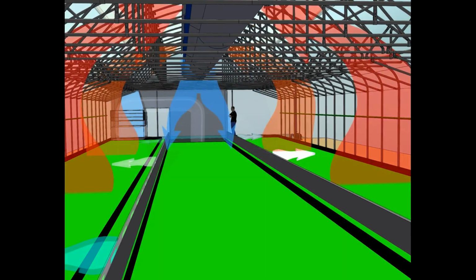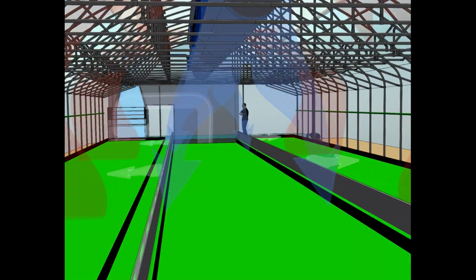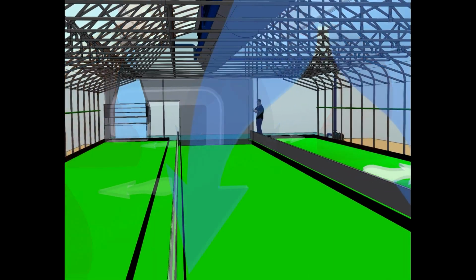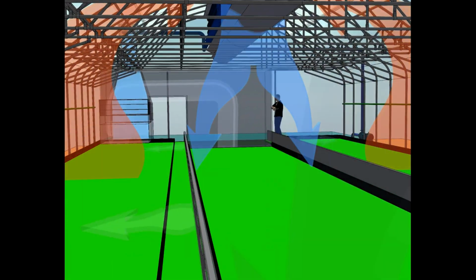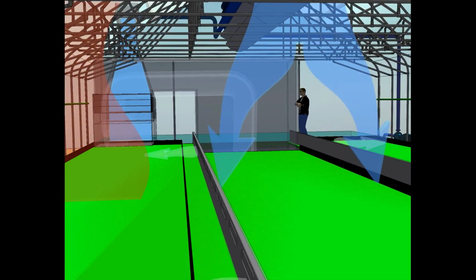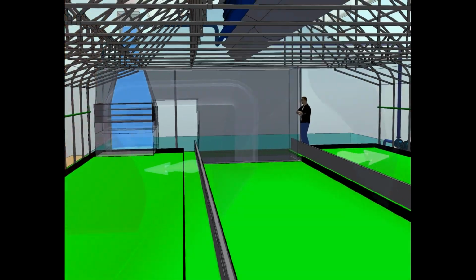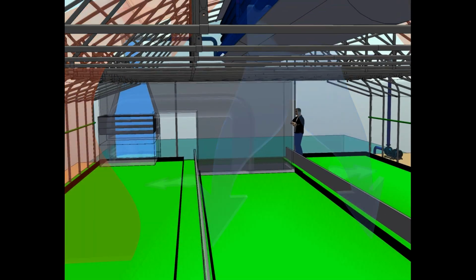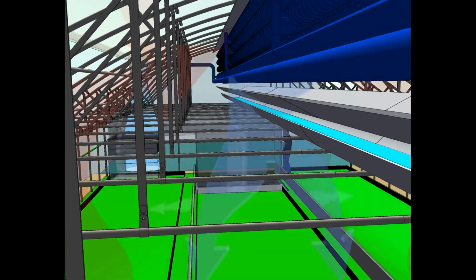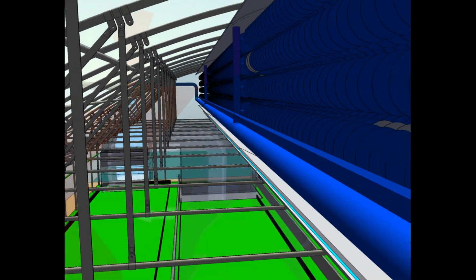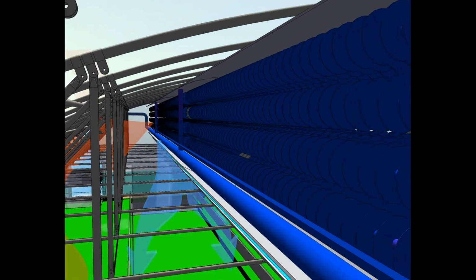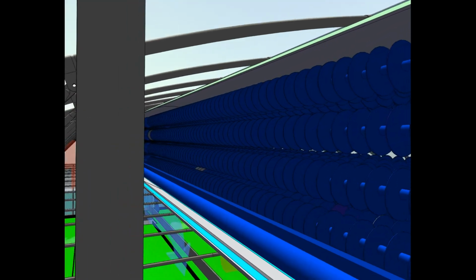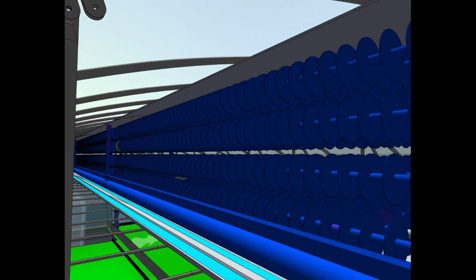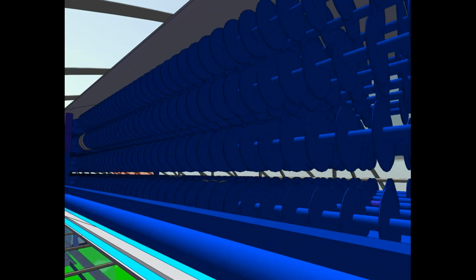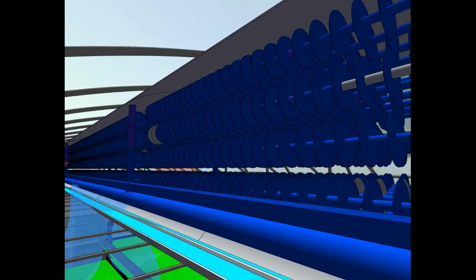Between the inlet and outlet manifold pipes of the heat exchanger condenser, running along the entire length of the greenhouse, there are coils of air cooling tubes with transverse fins. Moist heated air rising to the upper part of the greenhouse enters the area of finned heat exchange tubes, on which moisture condenses, and the air cools and falls down. With a small hydraulic resistance of the finned tubes, the air in the greenhouse is cooled quite effectively even in very hot weather. Drops of condensation from the finned surfaces of the cooling tubes fall into a slightly inclined tray and are directed by gravity to an underground fresh water tank.